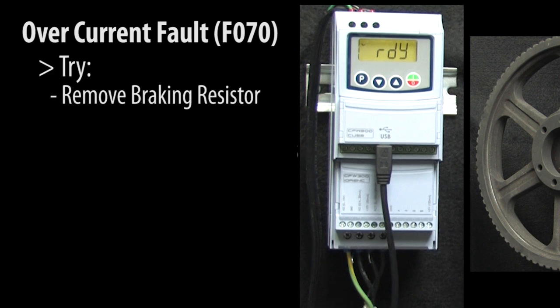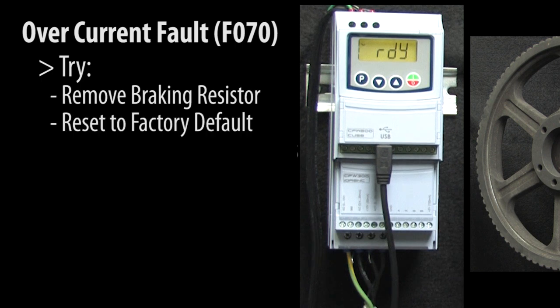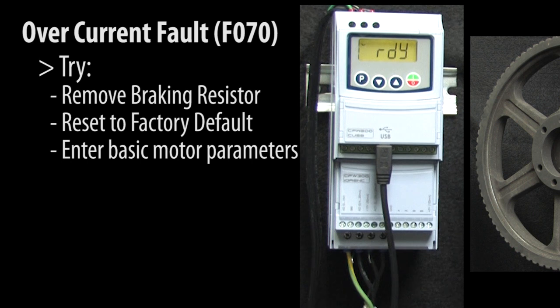Try removing any braking resistor you may have, resetting the drive to factory default and re-entering your basic motor parameters. Often that will get the drive running, and then you can slowly add the other parameters you changed back in until you find the one causing the issue. If the drive still doesn't run after all of that, try swapping it out with a known good drive.